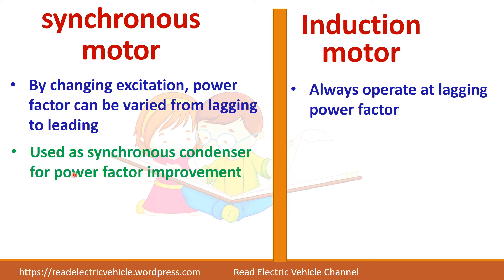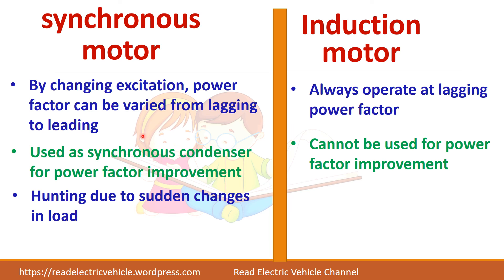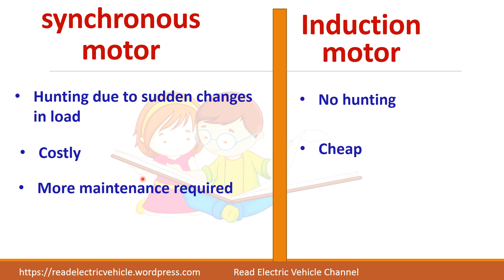Synchronous motor is normally preferred as a synchronous condenser so that it can be used for power factor improvement, whereas induction motor cannot be used for power factor improvement. Hunting is a problem in synchronous motor which is not present in induction motor. Synchronous motors are costly whereas induction motors are cheaper. Synchronous motor requires more maintenance whereas induction motor requires less maintenance.